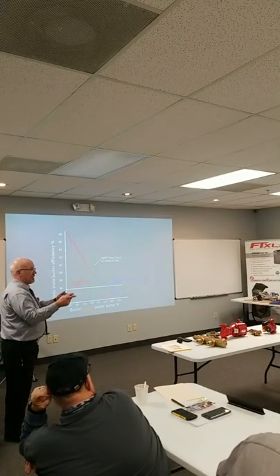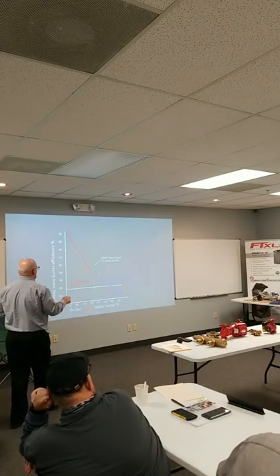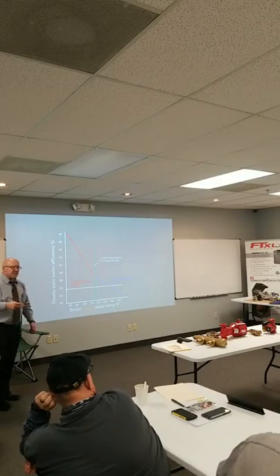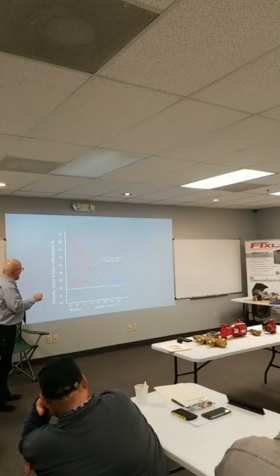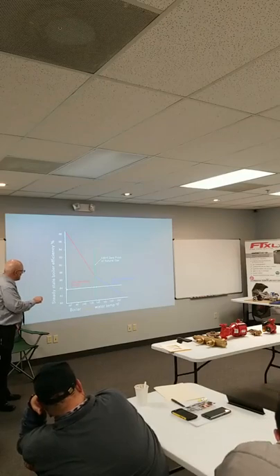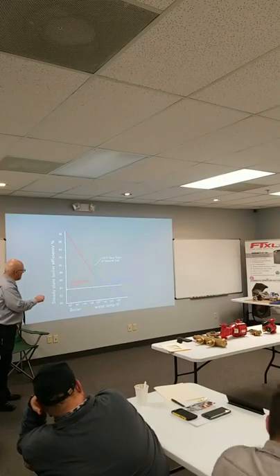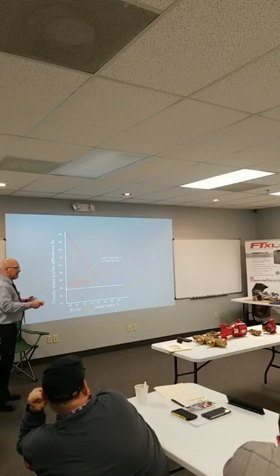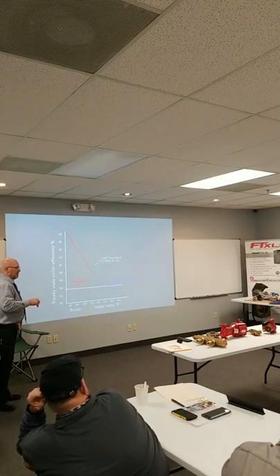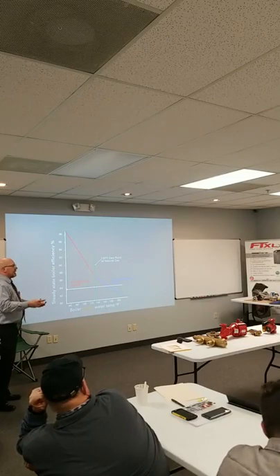But here's, somebody asked the question earlier, where's our dew point? Where do we start to condense? It's at 135 degrees, you'll see, somewhere in that water temperature. The flue temperature and the water temperature are very similar. Natural gas flue products. What about propane? Is it similar? I don't know the exact number for propane, but for the boiler side, we use the same number.